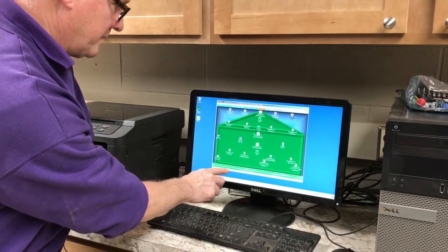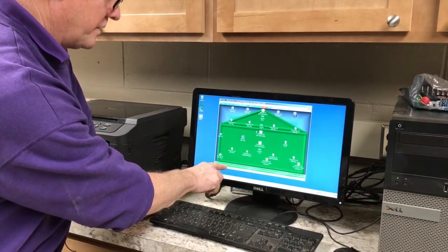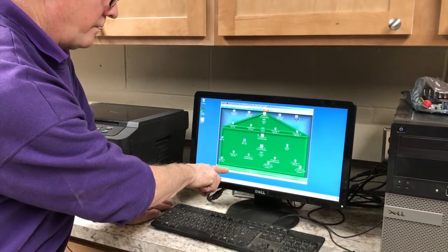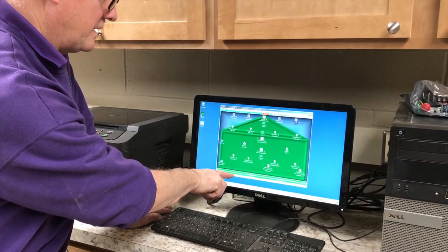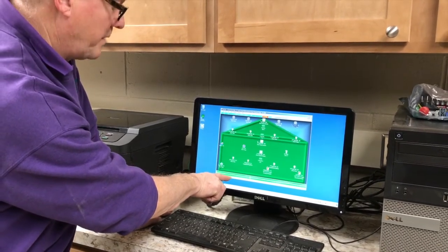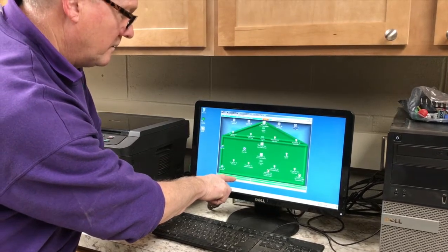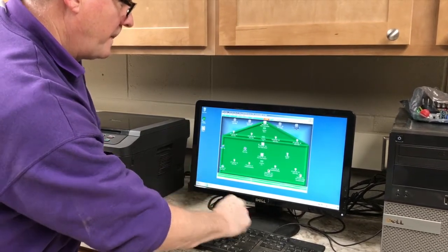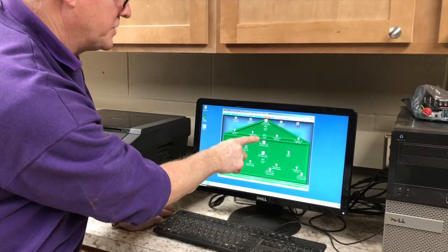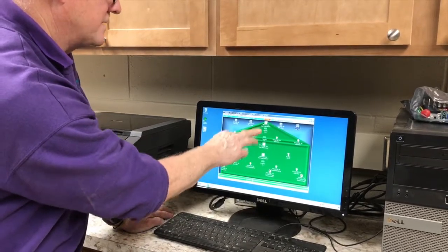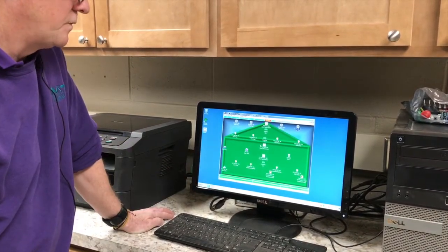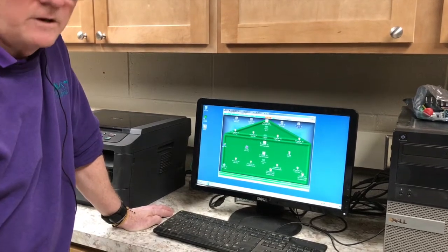It gives us the set points for the greenhouse, where it's going to warm when the temperature drops below 68 and cool when the temperature goes above 72 degrees. And then it also gives us our vent positions for our roof vents and the side vents. So at a glance, this will tell us what's going on within this greenhouse.